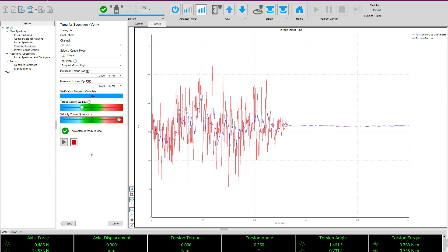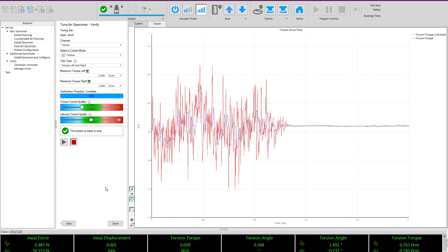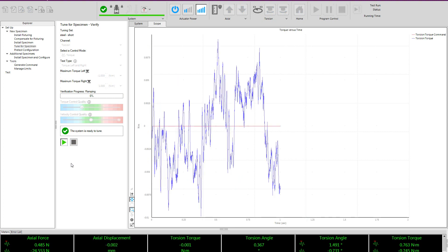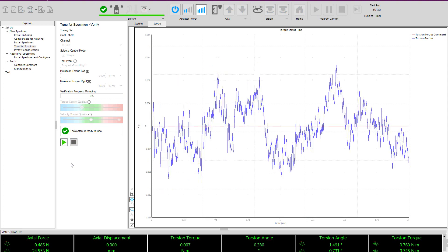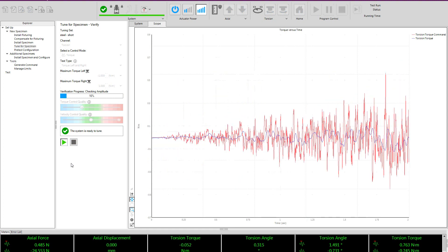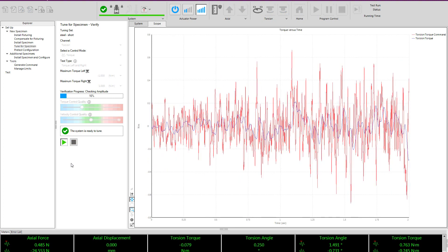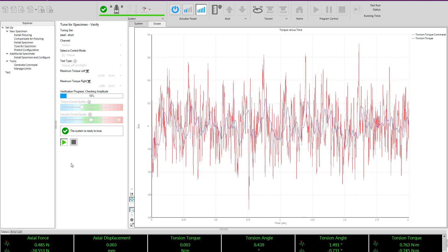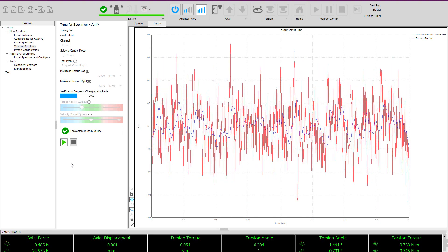Blue indicating a control mode that is on the cold side or the tuning being too low. Red indicating the tuning on the hot or too high of tuning. From here, you can simply drag the slider down into the range and re-perform the verify step, in order to make an adjustment to tuning and then re-evaluate the performance and stability of that tuning set.